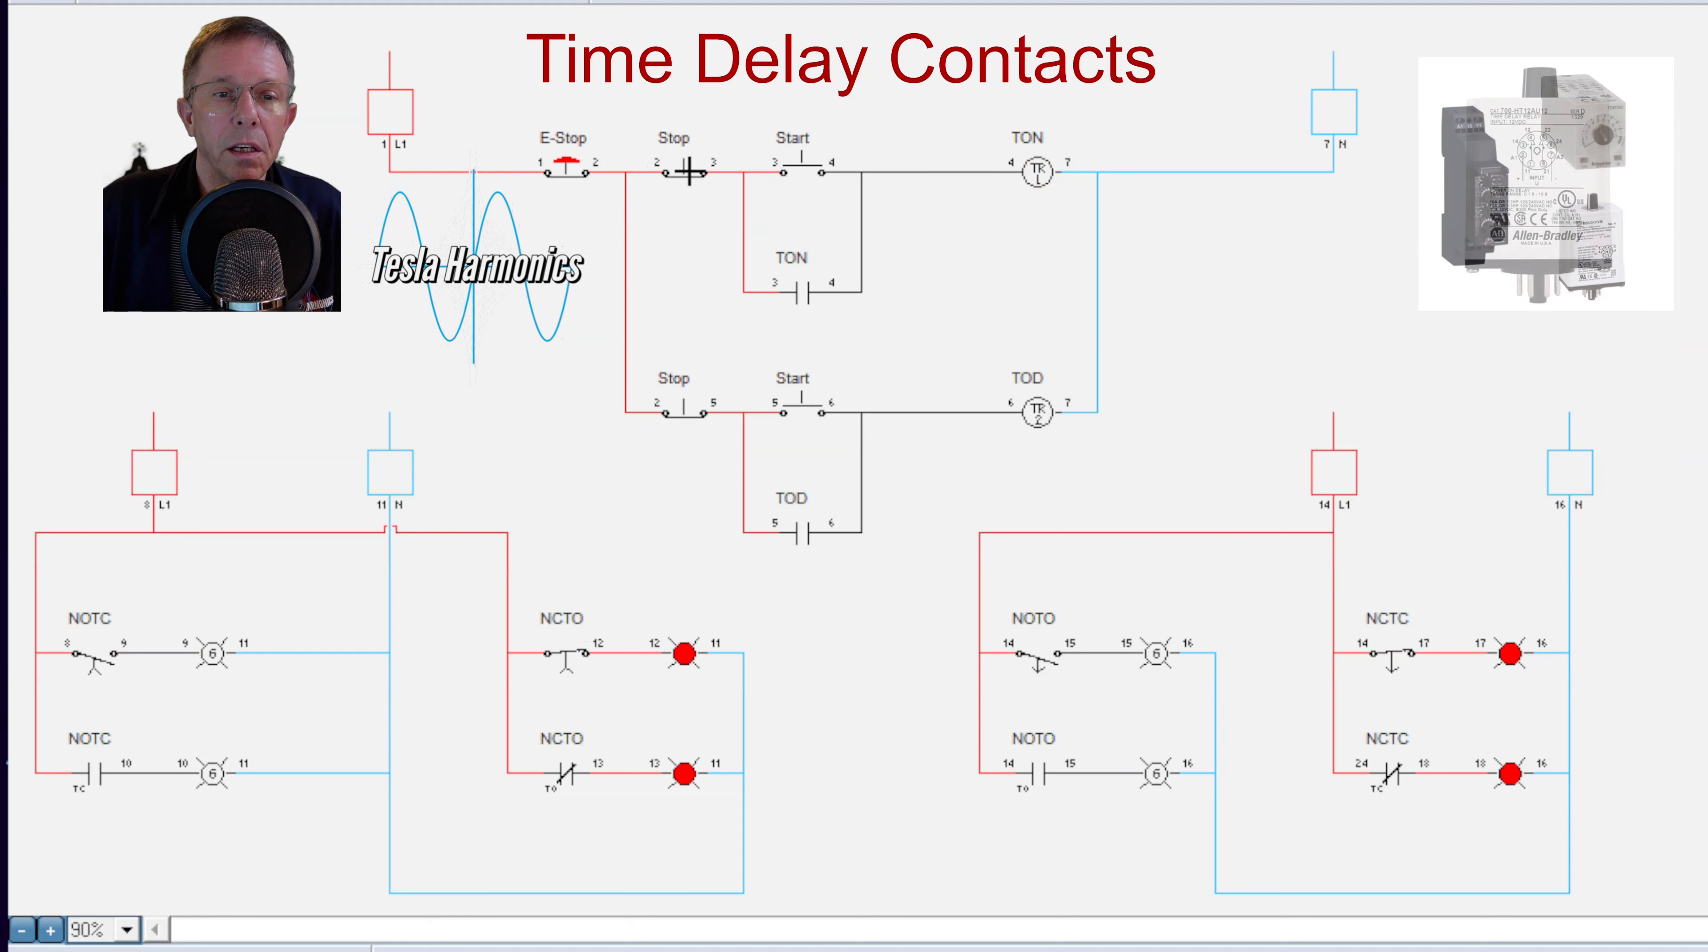an arrow pointing up. That means it's going to time to go up and close, so that's our time on delay. This means the same thing, except I show a normally open contact and I put a small TC by it for time closed.